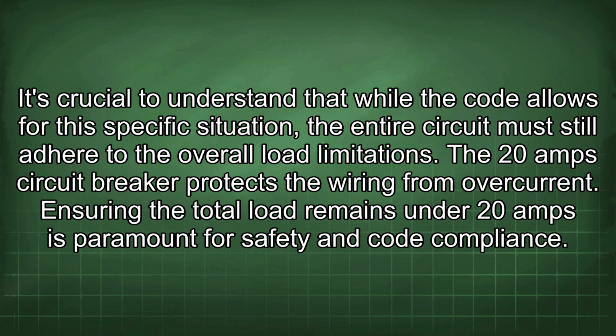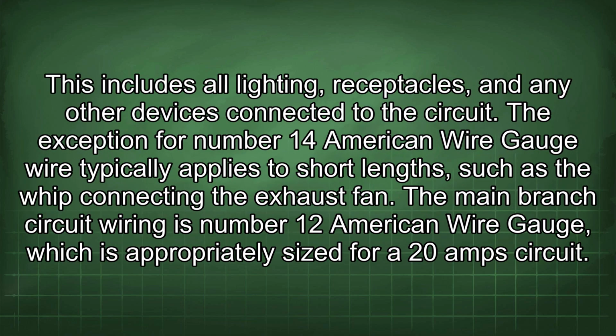It's crucial to understand that while the code allows for this specific situation, the entire circuit must still adhere to the overall load limitations. The 20 amp circuit breaker protects the wiring from overcurrent. Ensuring the total load remains under 20 amps is paramount for safety and code compliance. This includes all lighting, receptacles, and any other devices connected to the circuit.